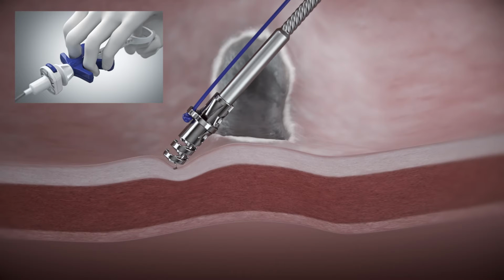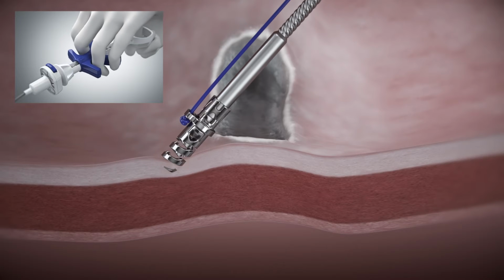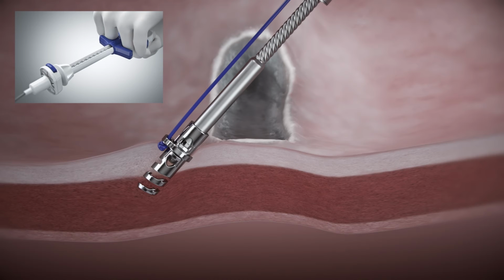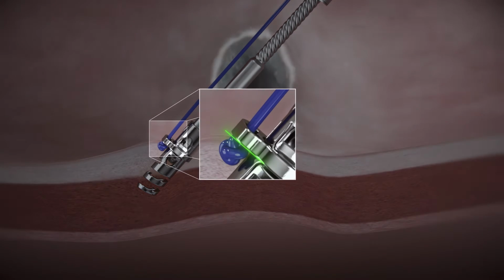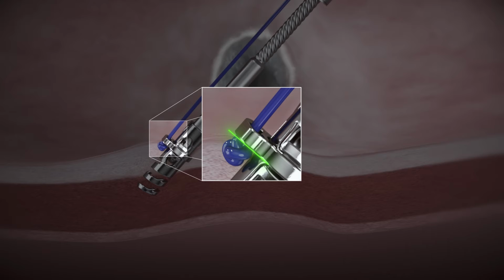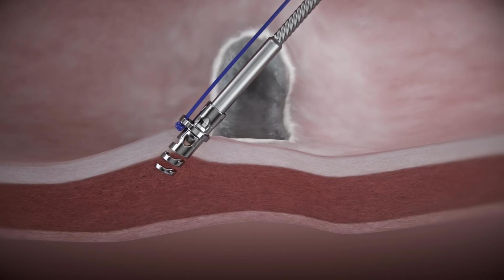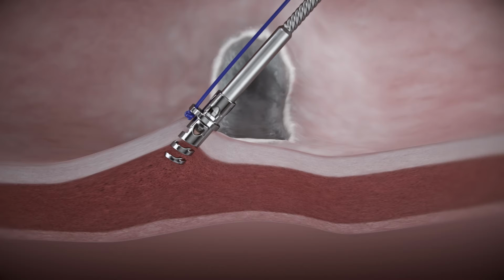While applying forward pressure to the catheter, drive the helix tack by slowly pulling the handle slider to the D position until the hard stop is reached. Visually verify that the helix tack eyelet is flush with tissue. Gently pull back on the device catheter to ensure adequate helix tack engagement.